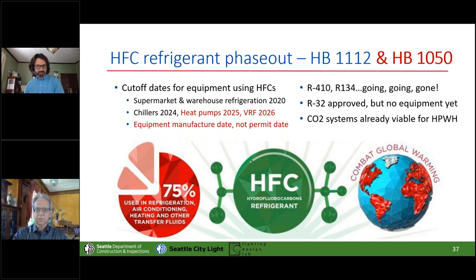So CO2 is a likely one, global warming potential of one, but it's worth saying it's high pressure systems. It requires very high pressure compressors, coils, piping. So for packaged equipment, not split systems, certainly not VRF, CO2 looks like a near-term future. And then the direct nearly drop-in replacement, it will take slightly different compressors and coil areas and whatnot, is R32. So R32 is grand, except it is slightly flammable. It's like this much flammable. It takes huge concentrations. Our code doesn't recognize slightly flammable versus really, really flammable. It looks at this refrigerant the same way it looks at a tank of propane. So at least until we get code changes, we're not going to get to do that.